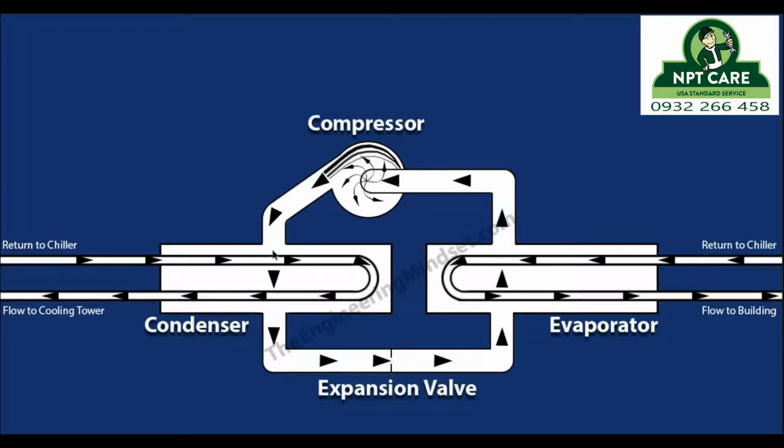The refrigerant comes in and condenses along the tube wall. It does not enter into the water, and it does not leave. It just condenses on there and continues flowing through, pushed by the static pressure until it hits the expansion valve. The expansion valve is just expanding that refrigerant, giving it a greater ability to pick up heat when it gets into the evaporator there. So these are the 4 main components and the 3 main circuits you need to know about. They will appear in every chiller, all types, sizes and shapes.